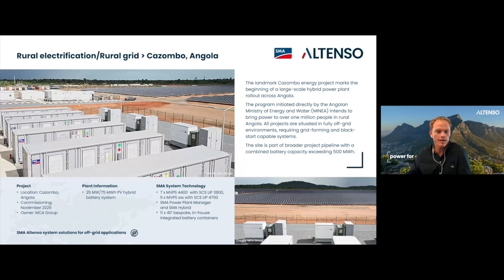And then lastly, just a project that's quite interesting. We inaugurated this at the end of last year, which is the Cazombo off-grid site. This is the largest off-grid PV plant in Africa, and it relies exclusively on PV and batteries with grid forming technology. So there's no diesel gensets on site. And this is now providing 24/7 power to 136,000 Angolans for the first time. One thing that's interesting about this project is that because of the funding requirements, there was a requirement that all the content had to come from Europe. And so we actually integrated the battery containers at our SMA headquarters in Germany. That just shows the engineering capabilities of Altenso, and the work that we're able to do from our factory.